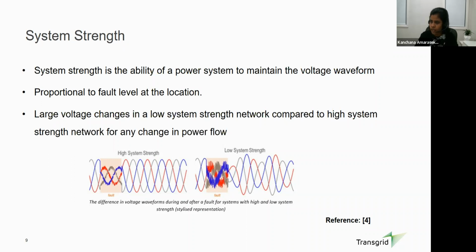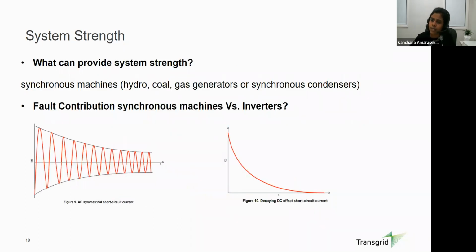Then I wanted to discuss what can provide system strength services. In traditional power networks, synchronous generators, whether hydro, coal, or gas, used to provide system strength services. Even synchronous condensers can provide these services. A synchronous condenser is basically similar to a synchronous generator, but it doesn't have a prime mover. And in the next part, I also wanted to show you the difference between the fault contribution of a synchronous machine and an inverter. The first figure is the symmetrical short circuit current of a synchronous machine, and this is the DC component.